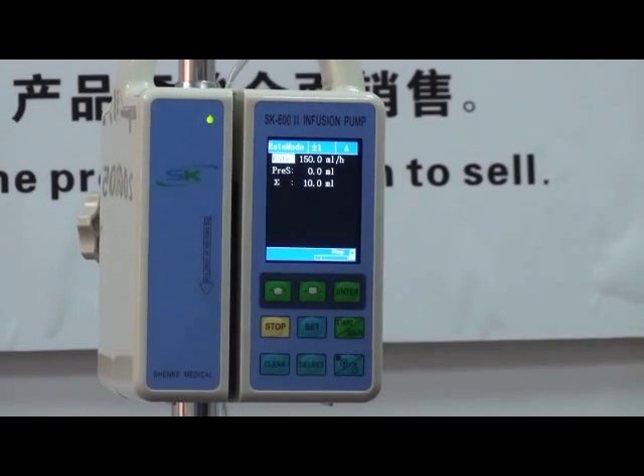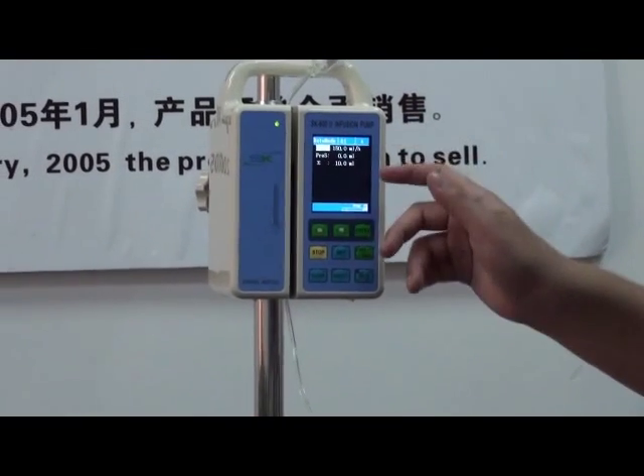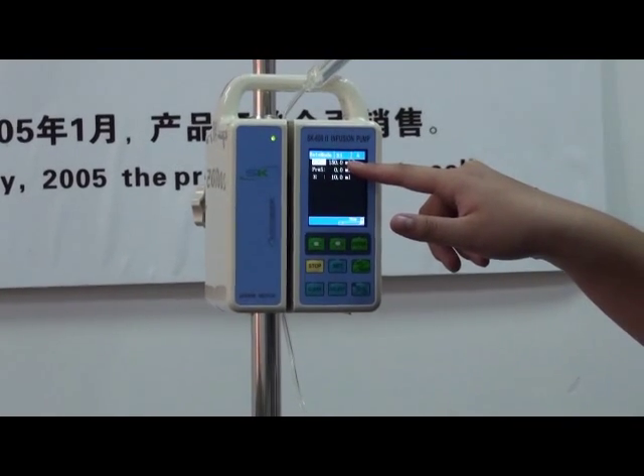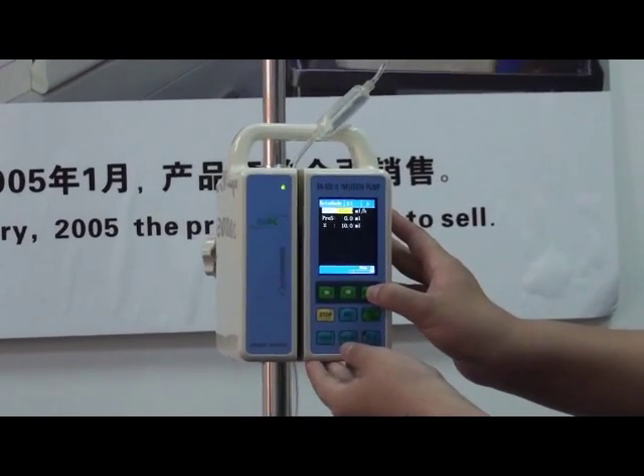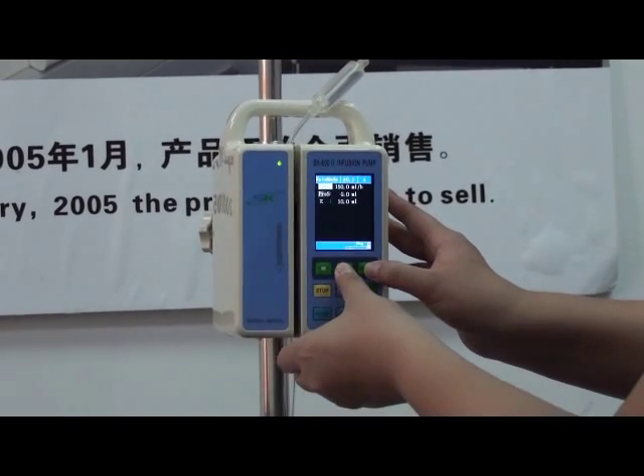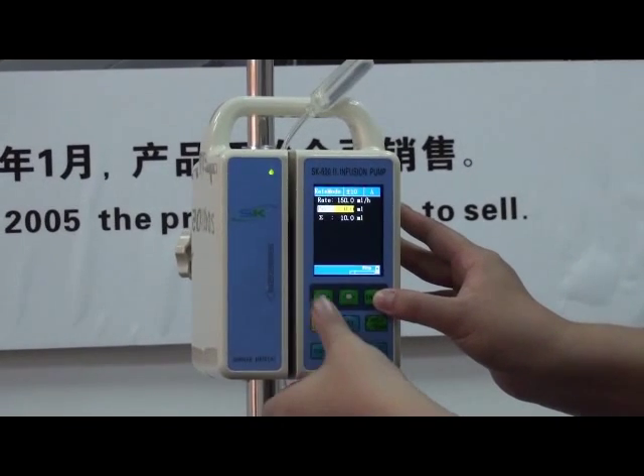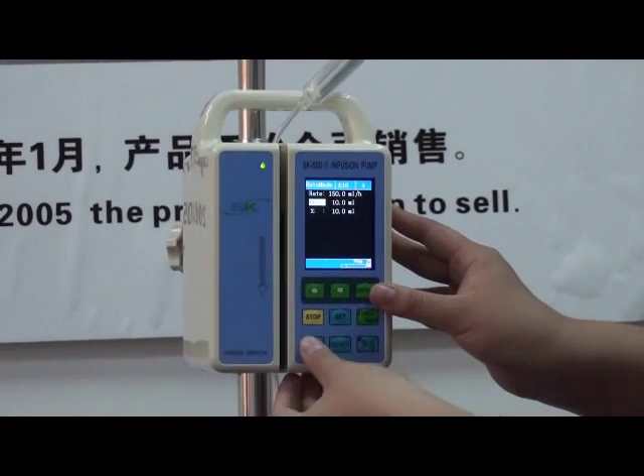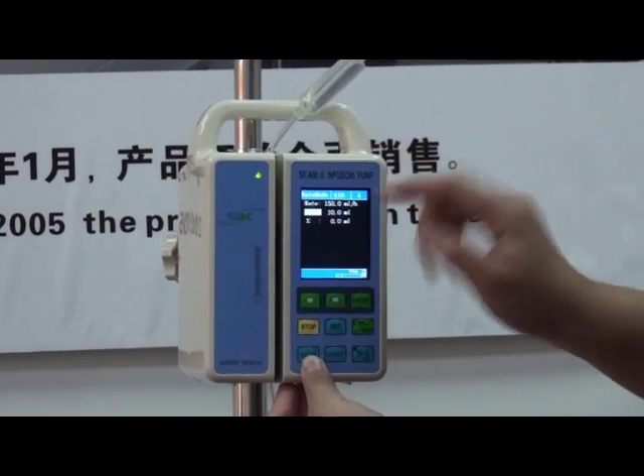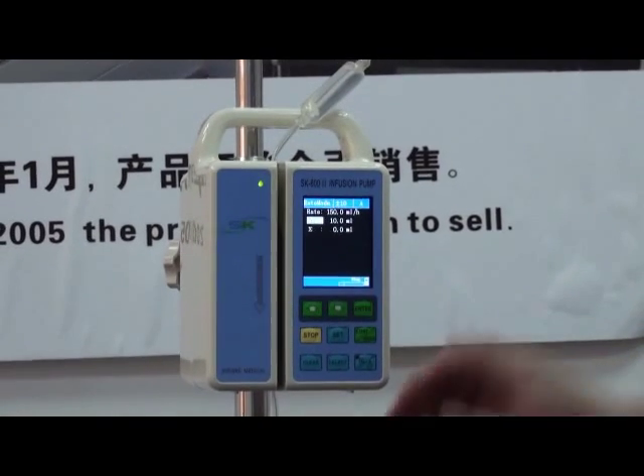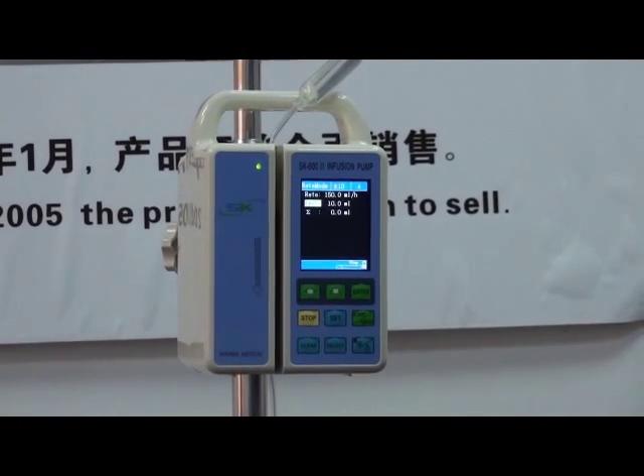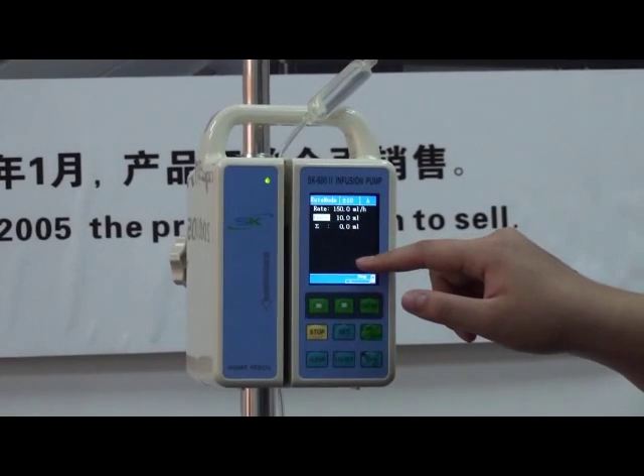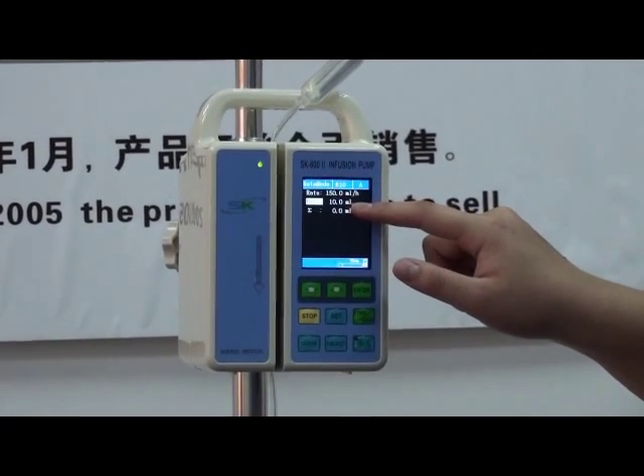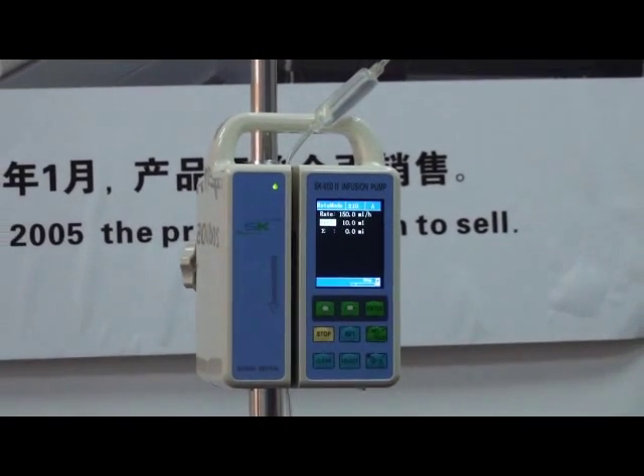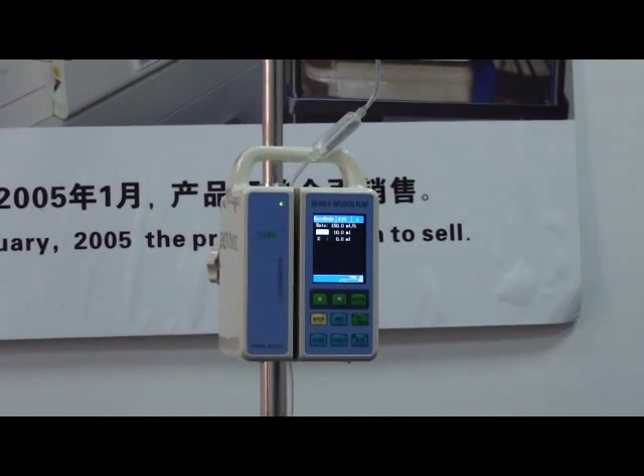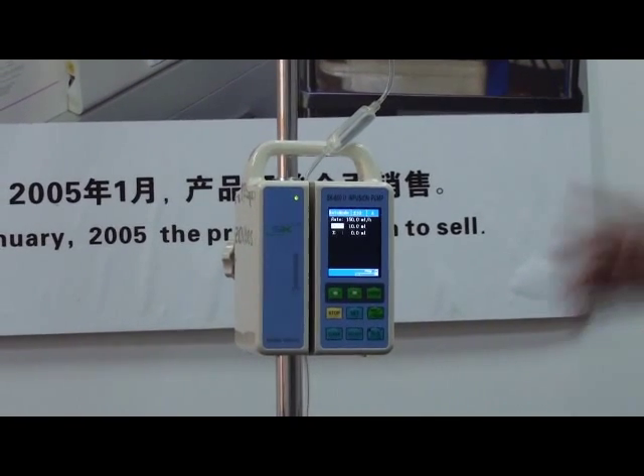Then use this IV set to test the accuracy again. Still the rate to be 150. Preset volume to be 10, and press Clear key to clear this accumulated volume to make it 0, and do exactly the same and check if the actual volume is the same as the preset volume. If it is the same, okay, there's no need to adjust the accuracy again. If it is not, try again.